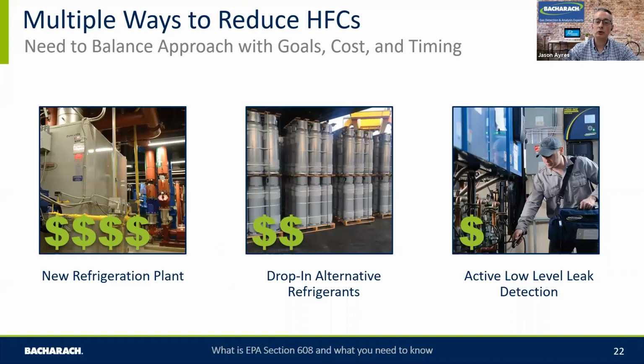And for this scenario, we'll talk about drop-ins. So keeping that existing plant operational, but replacing that high GWP refrigerant with a lower GWP alternative that will still allow it to operate in the same conditions, same pressures, temperatures, and also within the energy envelope. Like with anything we do to reduce our GWP footprint, refrigerant is one side of that, but it's not the whole picture. We need to be looking at energy as well. If we're looking at new systems or new refrigerants that will reduce GWP emissions through leakage, but they double the energy, is that the right technology that we should be looking at holistically as an industry and as a company? But drop-ins allow you a lower cost option to help on your refrigerant GWP reduction, and also with having the refrigerant available.